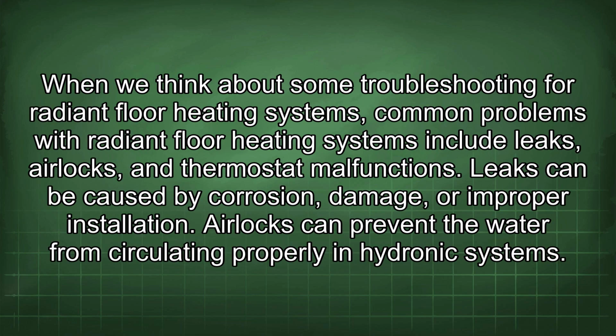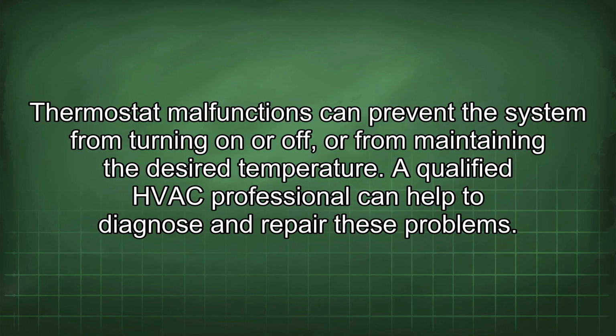When we think about some troubleshooting for radiant floor heating systems, common problems include leaks, airlocks, and thermostat malfunctions. Leaks can be caused by corrosion, damage, or improper installation. Airlocks can prevent the water from circulating properly in hydronic systems. Thermostat malfunctions can prevent the system from turning on or off, or from maintaining the desired temperature. A qualified HVAC professional can help to diagnose and repair these problems.